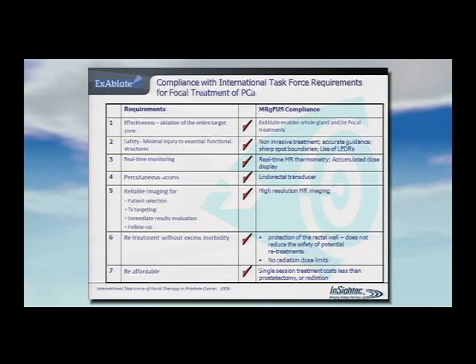The ExAblate 2100 prostate system. You can see the endorectal probe, motion unit, positioning. 990 elements phased array transducer, good control of sonication spot size, mechanical and electrical steering for coverage of the entire prostate. Single-use endorectal balloon, circulation of degassed cold water provides rectal protection.